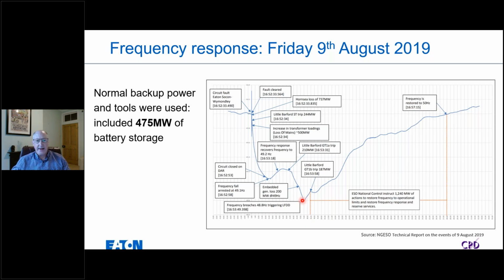So it was a draconian action, but we can see once those supplies are disconnected, we can see the grid frequency fairly quickly come back up to within tolerance limits. And if we look at this timestamp, this is 1657. So just under 5 minutes end to end for the transmission system frequency to start dropping, actions to be taken to restore that frequency, and for it to come back within tolerance. So a very short duration event. The impact was felt a little bit longer than that on the distribution system. It took about 45 minutes for the distribution system operators to restore all the supplies on their network.